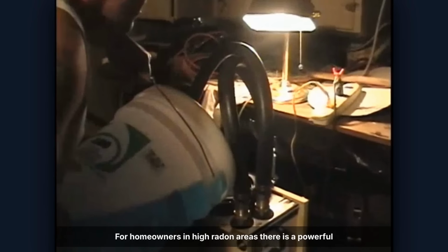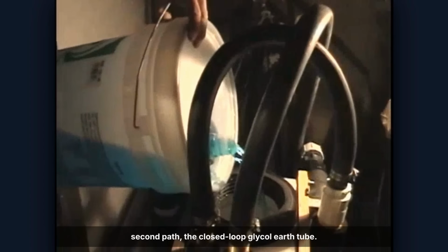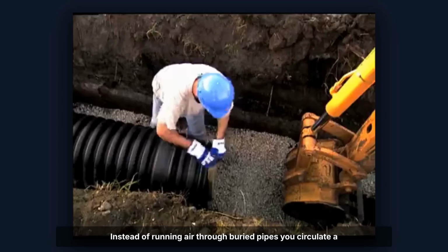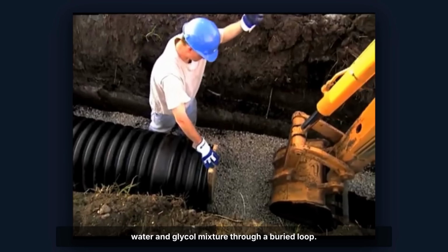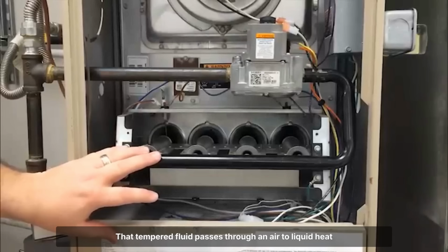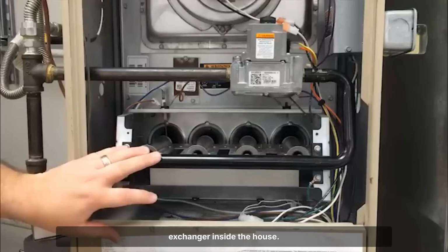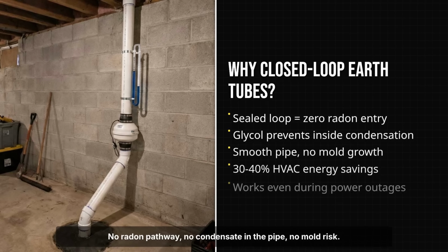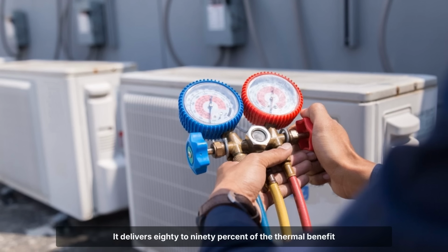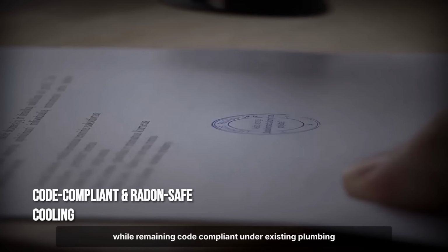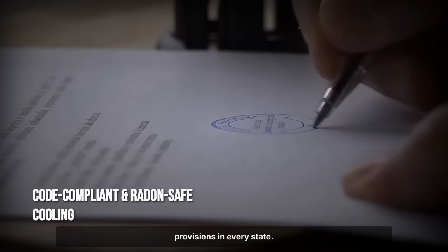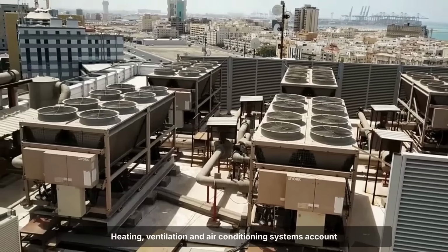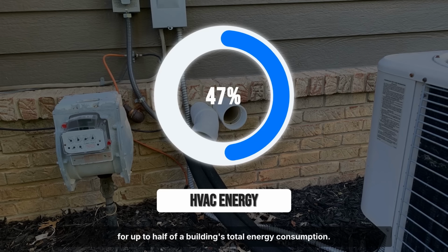For homeowners in high radon areas, there is a powerful second path, the closed-loop glycol earth tube. Instead of running air through buried pipes, you circulate a water and glycol mixture through a buried loop. That tempered fluid passes through an air to liquid heat exchanger inside the house. No radon pathway, no condensate in the pipe, no mold risk. It delivers 80 to 90% of the thermal benefit while remaining code compliant under existing plumbing provisions in every state. Heating, ventilation, and air conditioning systems account for up to half of a building's total energy consumption. Earth tubes attack that number at its root.